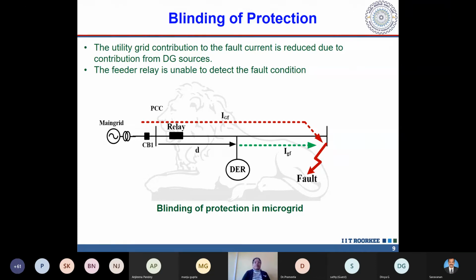But if the same fault is incepted in front of a synchronous based renewable source, so what are those? Like small hydropower plants, and the diesel generator sets I showed in the first figure of the microgrid. Those diesel generators are synchronous based generators. In front of that, if the fault is incepted, of course there is no inverter, so the fault current is no longer clamped to 2 per unit. Rather, it is increased to 5 per unit or something, sometimes more than that also.